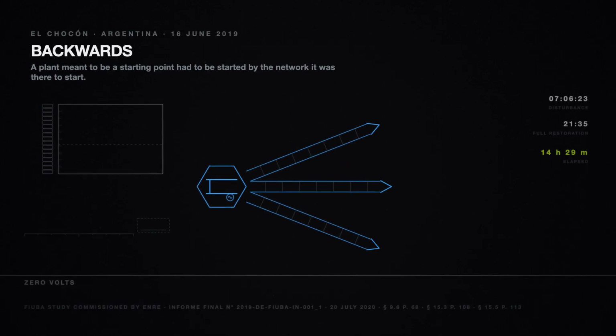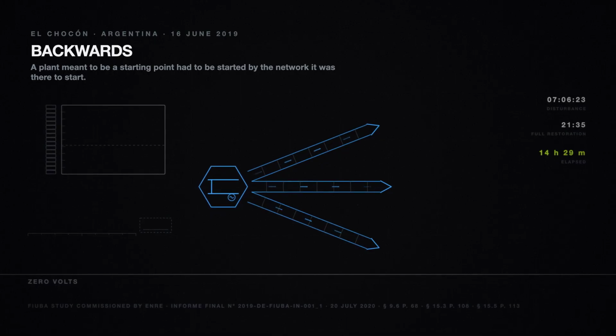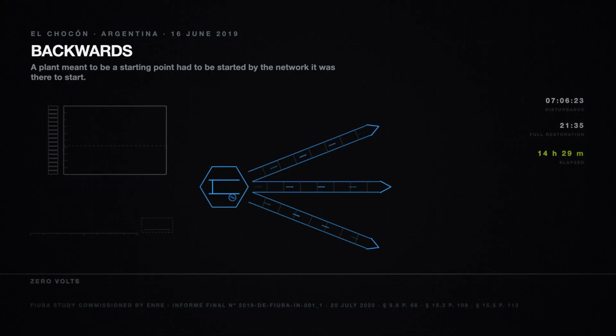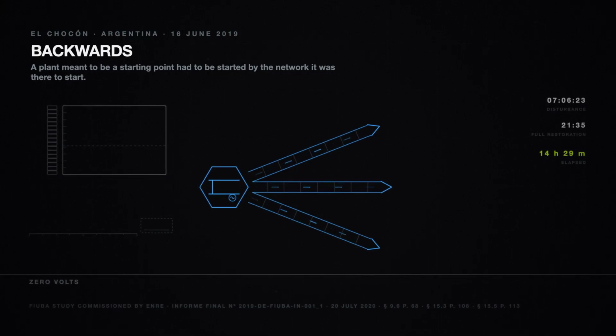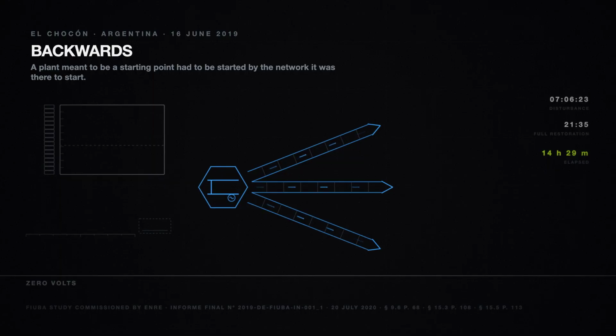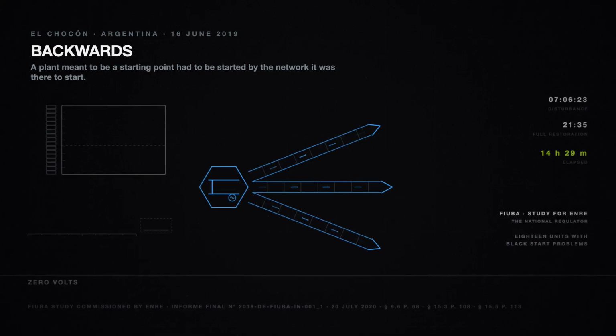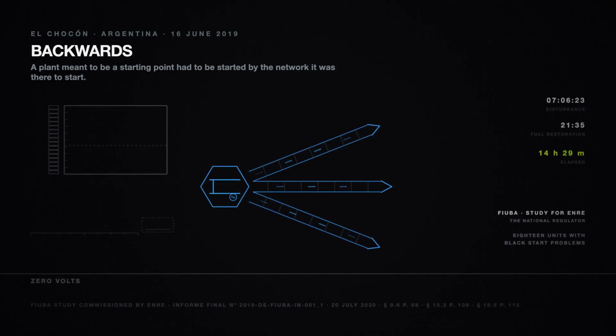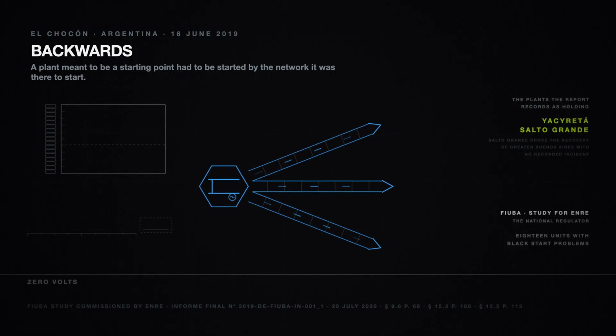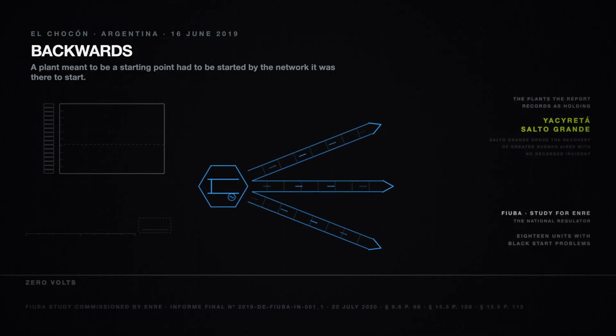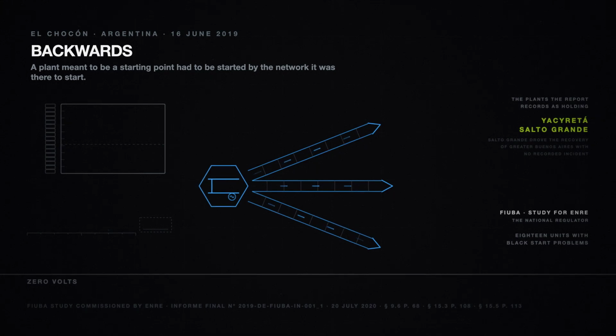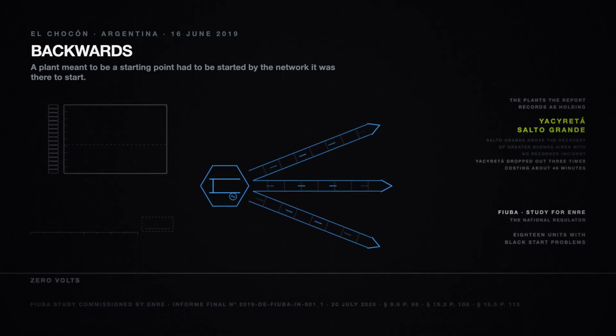Argentina, the 16th of June, 2019. The system collapses at 6 minutes past 7 in the morning. Full restoration comes at 9:35 that night, 14 hours and 29 minutes. A study for the national regulator went through the restoration machine by machine. 18 units had black start problems. 2 large hydro plants carried it, Yacyretá and Salto Grande, which drove the recovery of Greater Buenos Aires with no recorded incident. Even they were not clean.